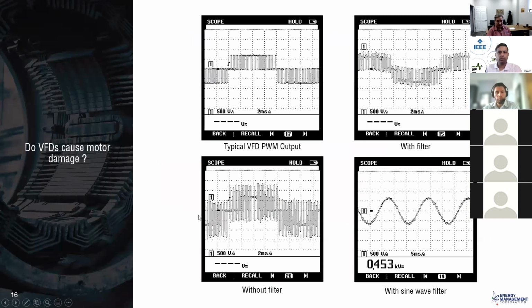So here's a little bit of background: here's our typical PWM waveform. You could call that a lab waveform, but it's also not atypical in most installations. But this one you see right here is just a data center with only maybe 200 or 300 feet of cable. It surprised us to see that kind of waveform. Now recognize that when you look at these divisions of 500 volts per division, we're looking at about 650 to 750 volts peak on the DC bus. These peaks are going well over 1,200, maybe 1,300.